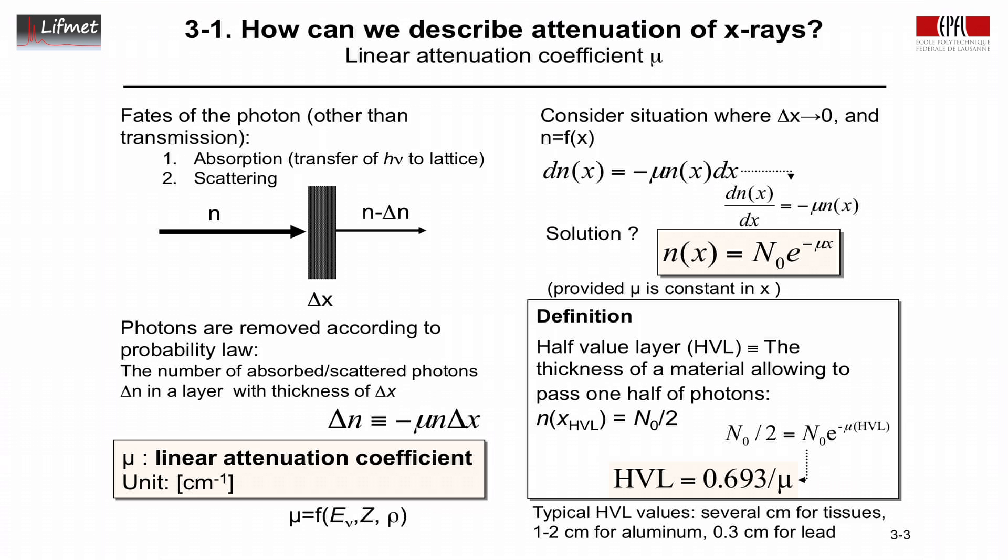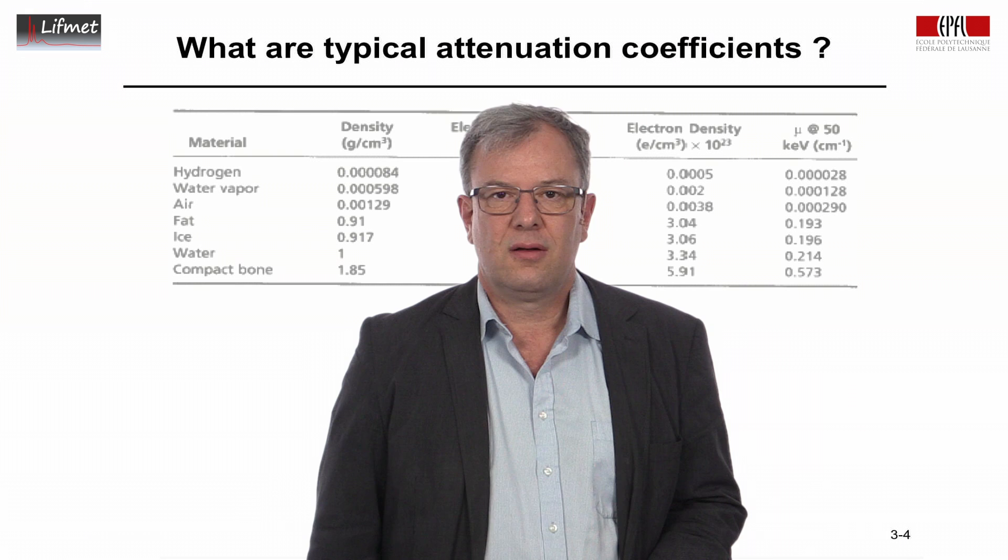And so, what are typical half-value layers here? They are given, typically for tissues, it's several centimeters. It depends on the X-ray that's being used. For aluminum, it's on the order of 1 to 2 centimeters, and 3 millimeters for lead, 0.3 centimeters here.